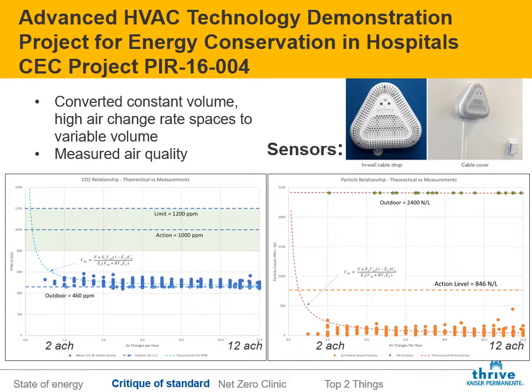A couple of amazing things pop out of this study right away. The first one is that this data very quickly debunks the idea that 12 air changes is better than 2 air changes, that just doesn't hold up in the data. You can kind of see that the levels are pretty much the same. If that surprises you, by the way, then you're not alone. It surprises me. I think we all grew up believing that 12 air changes per hour is fundamentally always going to be better than 2 air changes per hour.